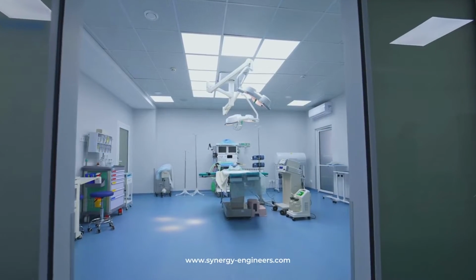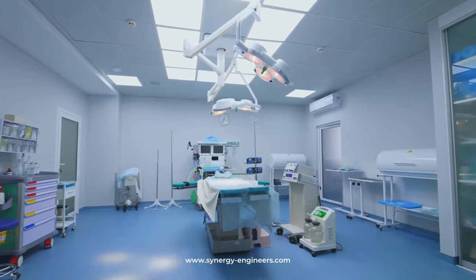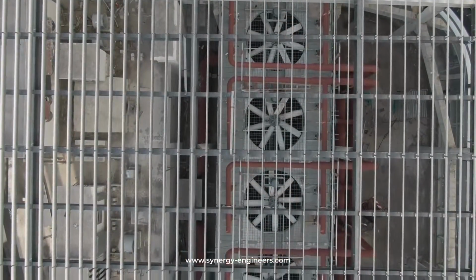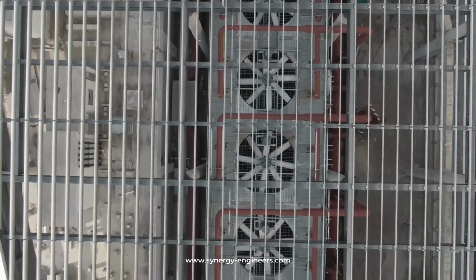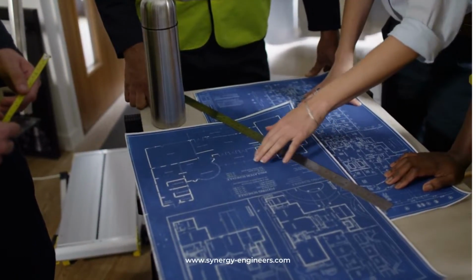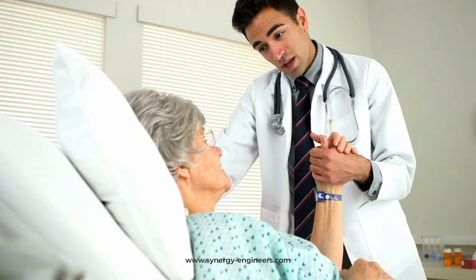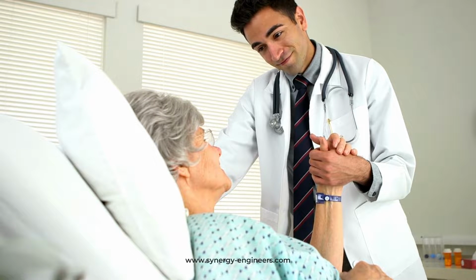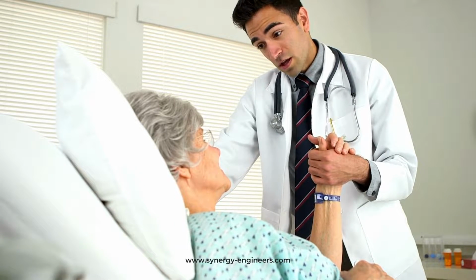Single fan systems typically present a single point of failure, and that's a massive risk, especially in hospitals when those air handlers and those fans are serving critical spaces. When we go to a fan array system with multiple fans within that array, they're more reliable and require less maintenance than belt-driven fans because they have fewer moving parts. When one or more array fans fail, the other fans can compensate automatically. There's no loss in performance and no risk associated with any type of patient safety or comfort issues downstream.